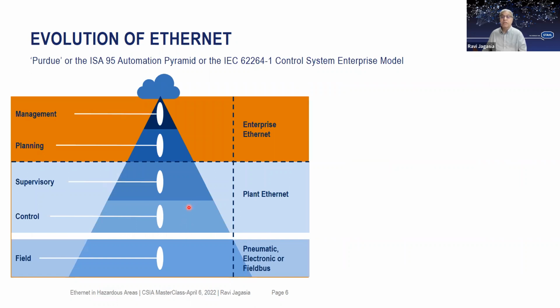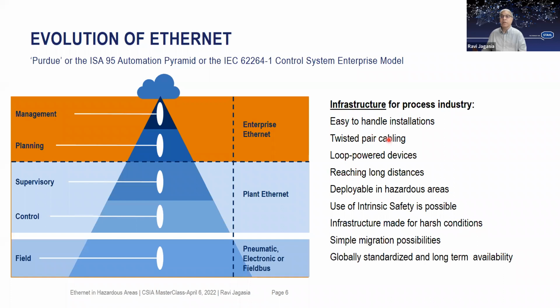And from the control systems into the supervisory systems and up to the enterprise level for the manufacturing execution systems, you had Ethernet all along. This meant that there was no Ethernet into the field. And if we wanted to do that, there were many challenges. We had to take care of twisted pair cabling. We had to ensure that the solution would be loop powered because we love to work with two-wire field devices. The plants are quite long, especially when you run the cables in the cable trays, and that becomes a challenge.